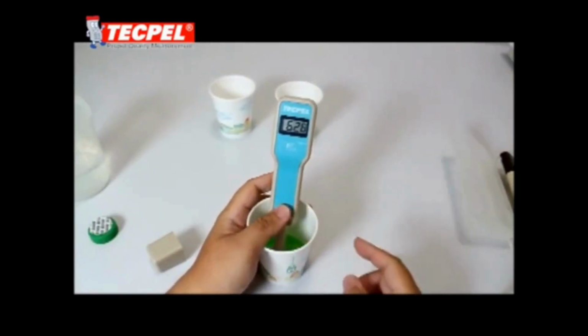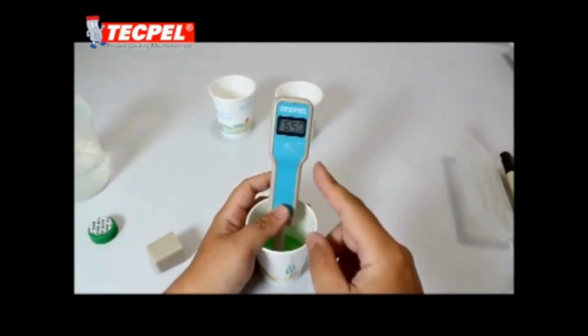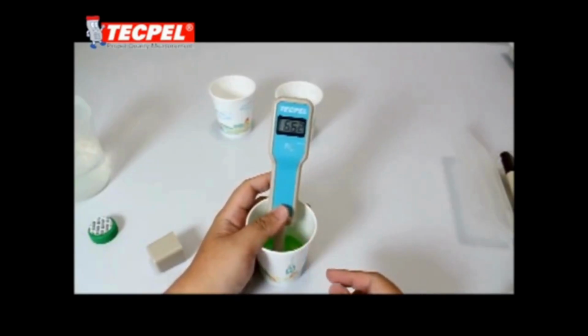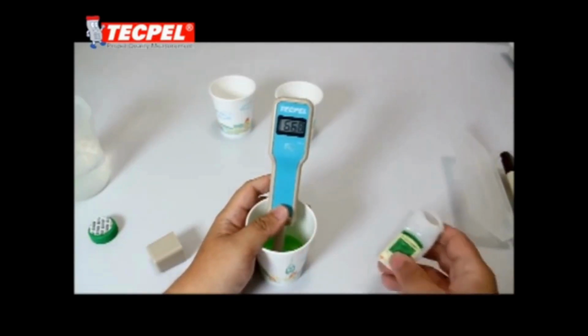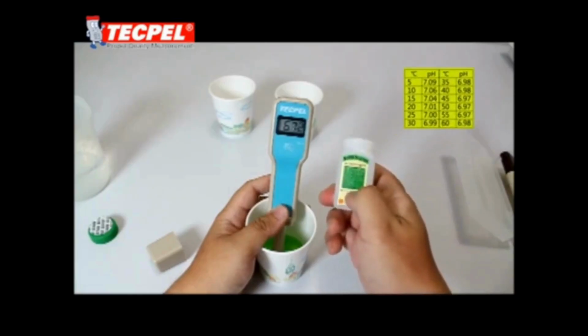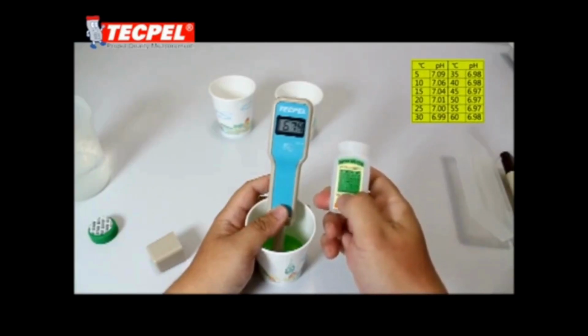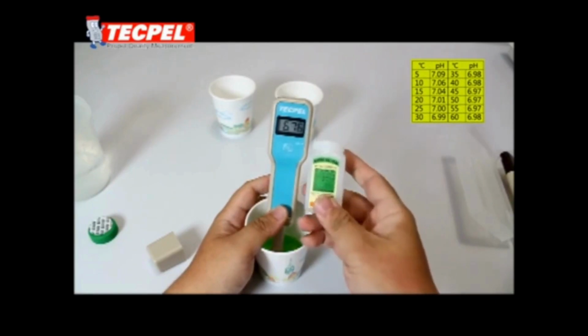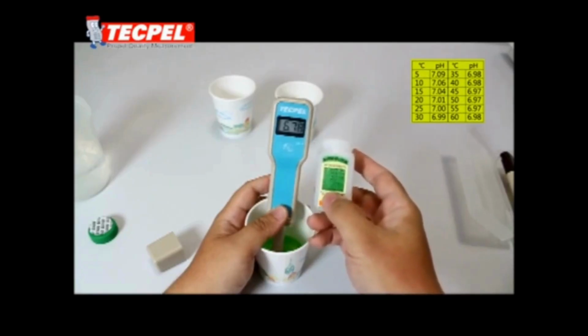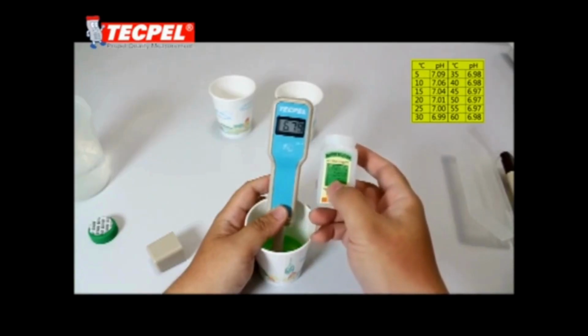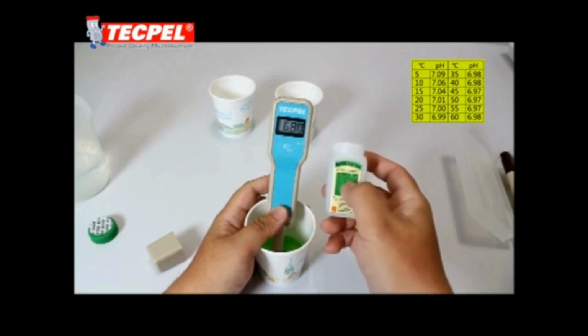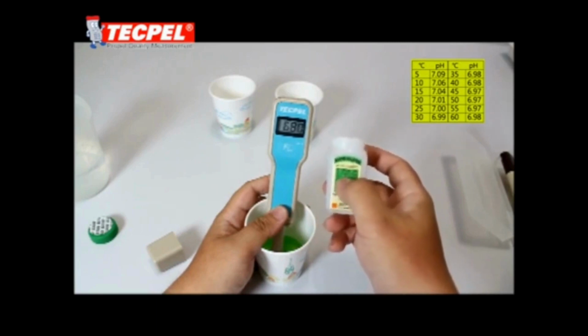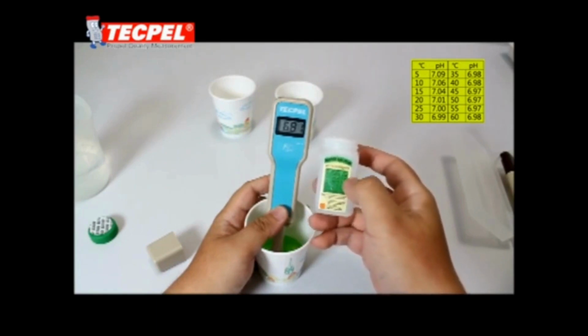However, you may notice slight changes depending on the surrounding temperature. The bottle of the standard buffer includes a reference table showing how temperature affects the pH value. At lower temperatures, the reading may shift slightly toward the alkaline side, while higher temperatures may cause the reading to shift slightly toward the acidic side. This is a normal chemical behavior, and the calibration process allows us to correct for this variation.